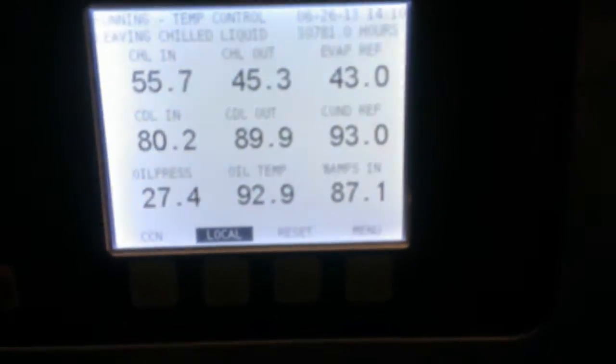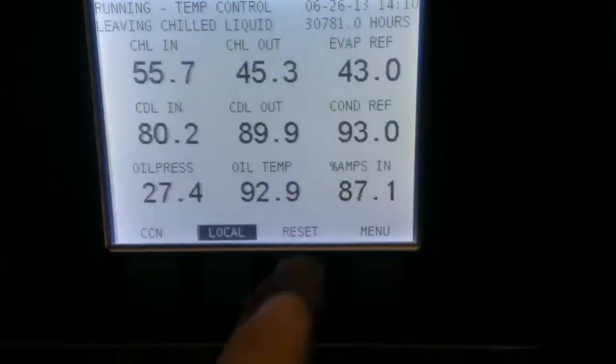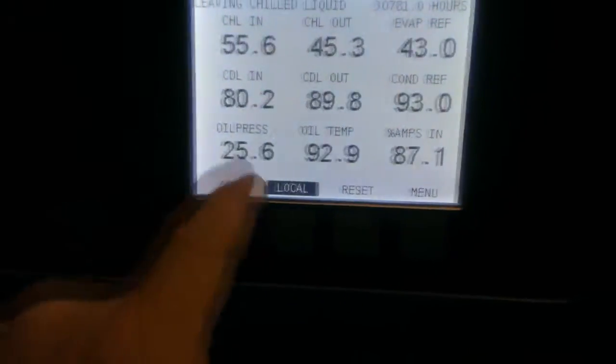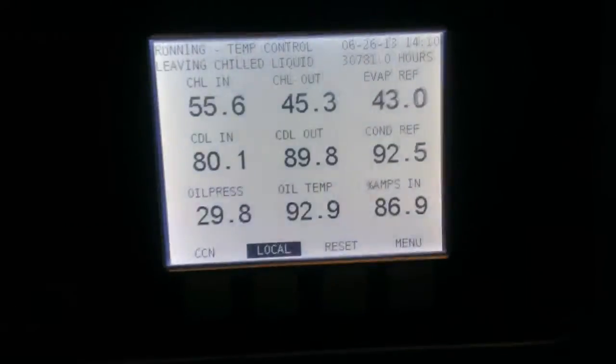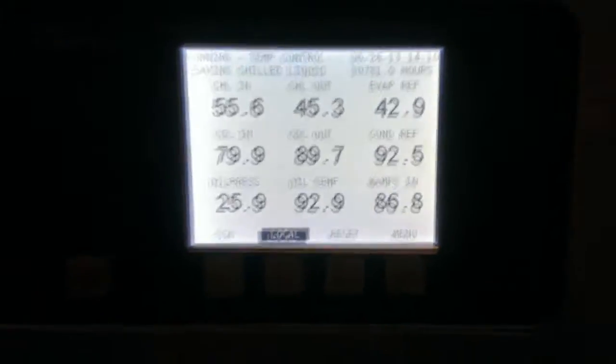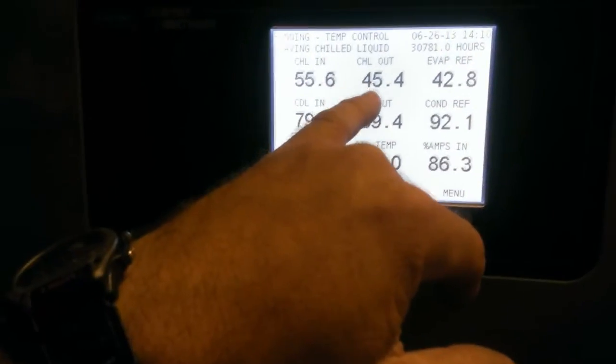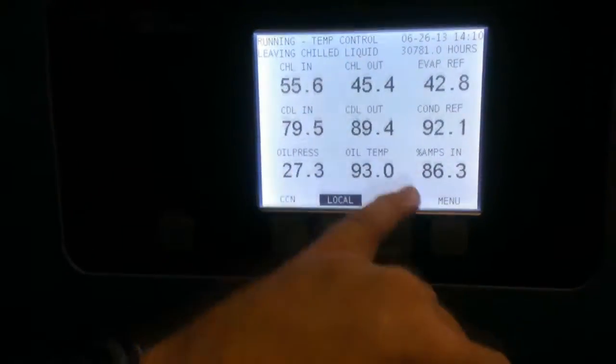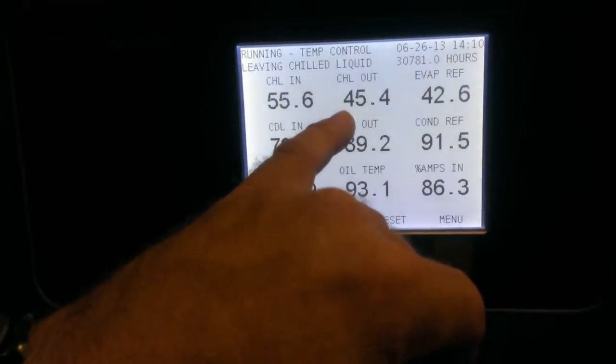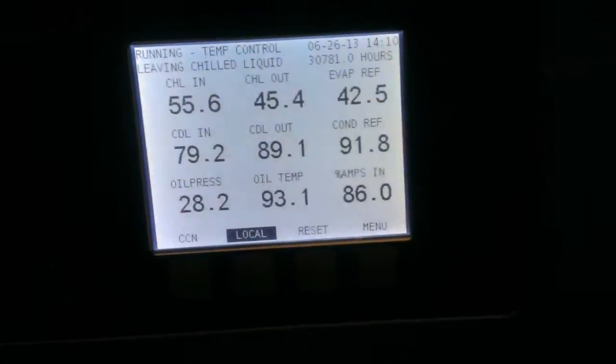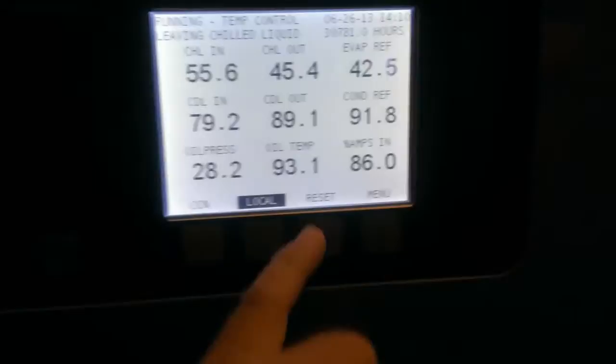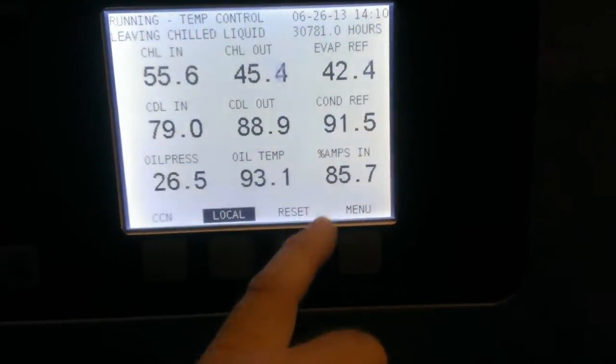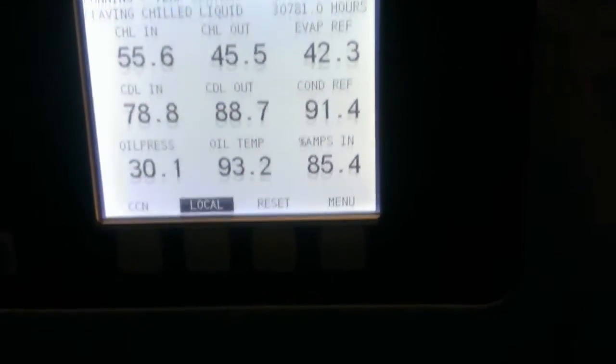It's really rocking now. 87% of capacity. It didn't, it's a hot day. It's over 106 out, I think, right now, outside. So when I switched from the other chiller to this one, the loop temperature got up there a little bit before this one fired up. So it had to catch up a little bit. It's still ramping up just to maintain the output. The water's, yeah, 45, it's not going down anymore, so.